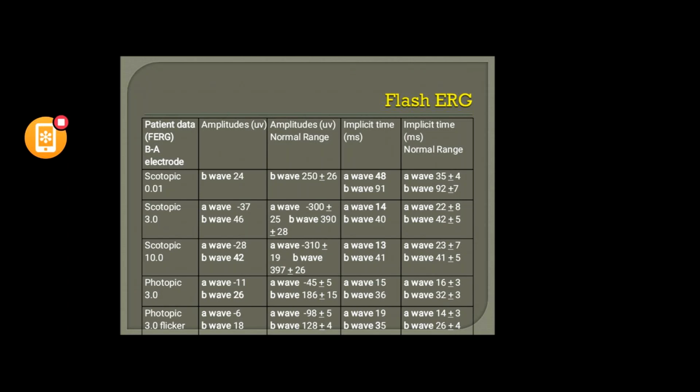Suppose you have electrode X and electrode Y. If your normative data is based on electrode X, you must perform the test on a patient with electrode X only, not electrode Y, because you do not have normative data based on electrode Y. So your performance level would be compatible with the X electrode.